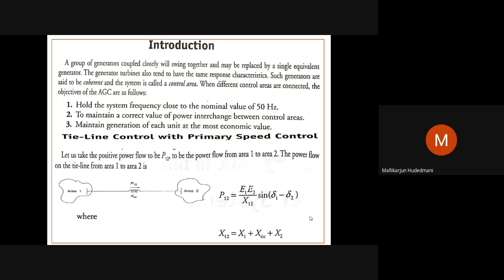Then we have some parameters to be understood: how exactly power flow occurs among the control areas, and what are all the things that the control areas need to adhere to. The first parameter: when different control areas are interconnected to one another, definitely the automatic generation controller installed in area 1, area 2, area 3 has certain objectives. They have to look after their own generation and demand in their area effectively, making the resources optimally utilized, meeting the end users' desired specification, and they should see to it that they are able to meet the requirement of the neighbor corporation if they have accepted an agreement of delivery of power or borrowing of power. We call it trading.